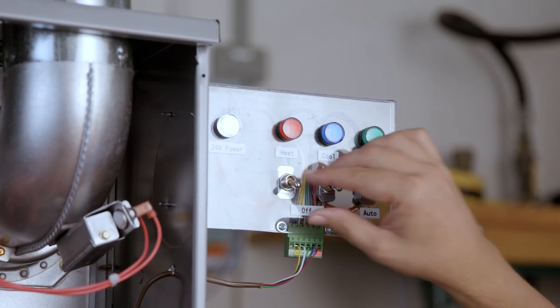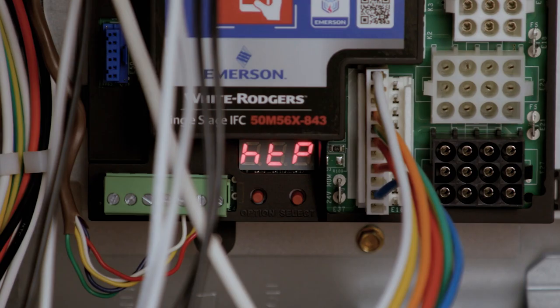To verify proper ignition, make a call for heat. During an active call for heat, cool, or constant fan, the LED display will alternate between up to three status indicators. The first will display the active call from the thermostat. If applicable, the active motor speed selection will also be displayed alongside flame current in heating mode.